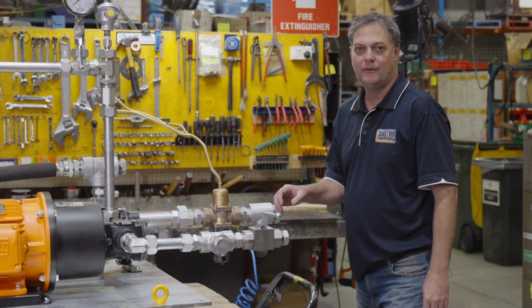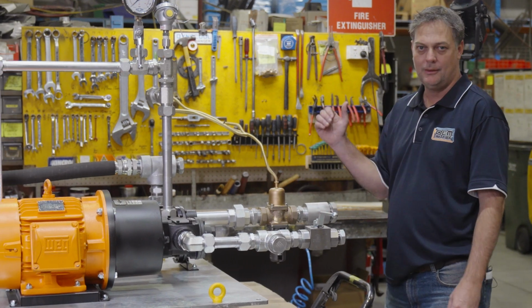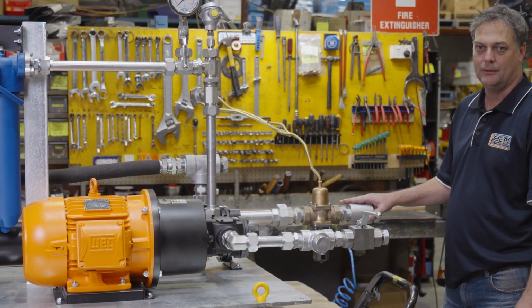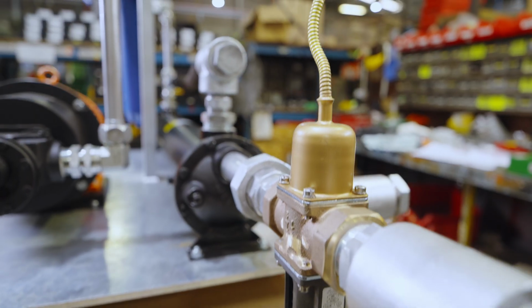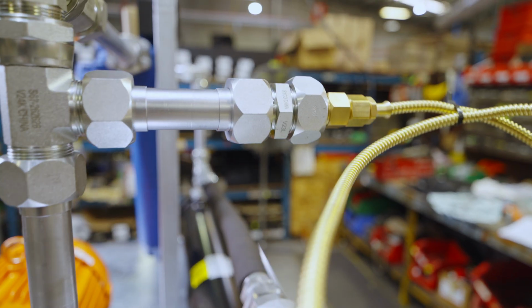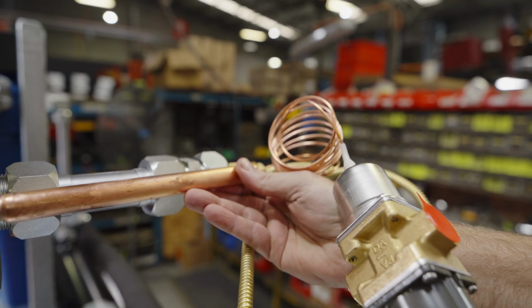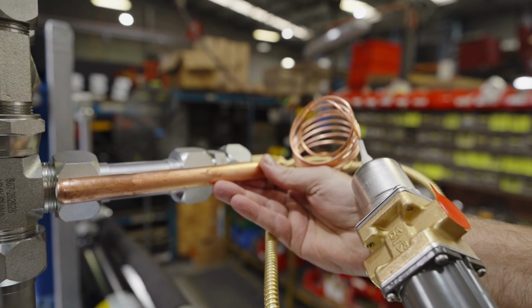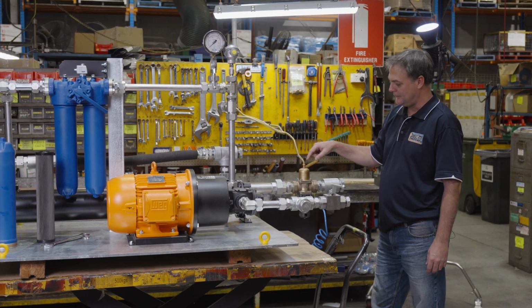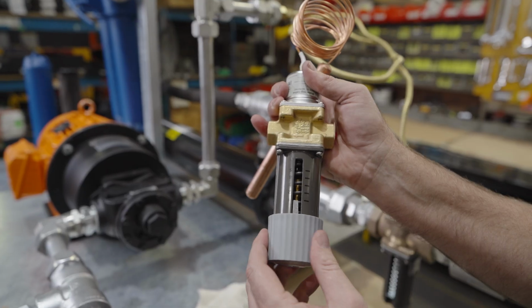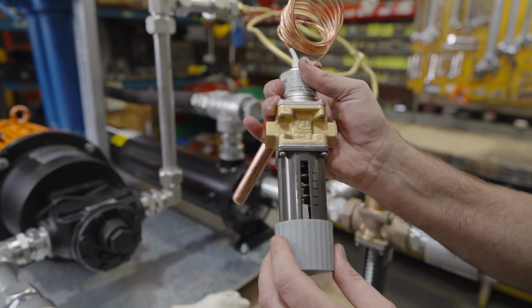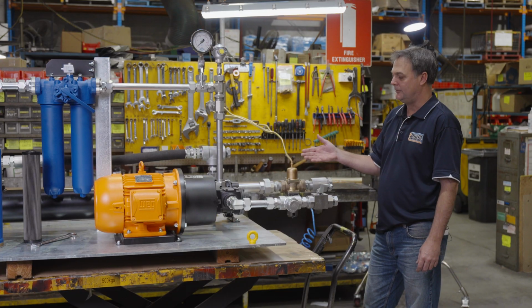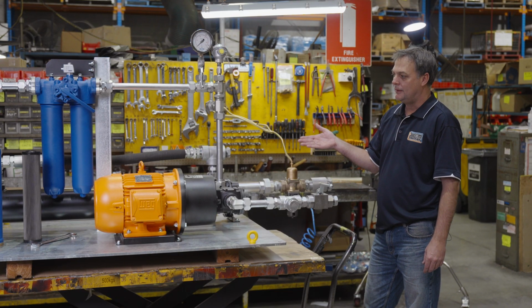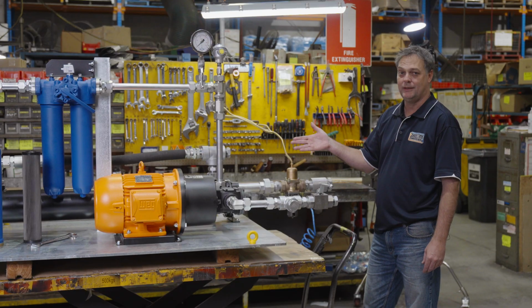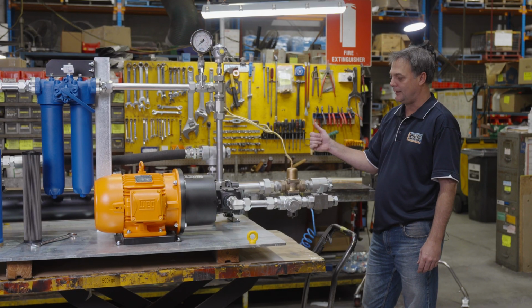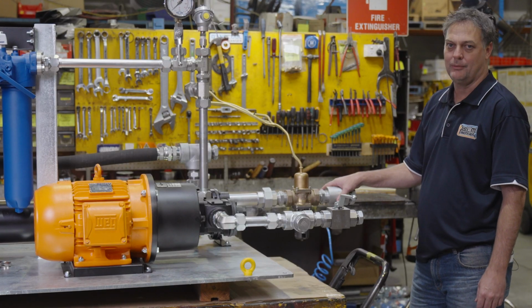What also helps control the temperature of the oil returning to the gearbox is the water control. Here, this unit here is equipped with what we call a water-modulating valve. This unit uses a bulb sensor which plugs into the hot side of the oil. That sensor is calibrated with the valve so that it can control the water flow in and out of the heat exchanger. This ultimately allows the unit to cool only when it really needs to cool, but also help maintain a constant temperature of oil going back to the gearbox.